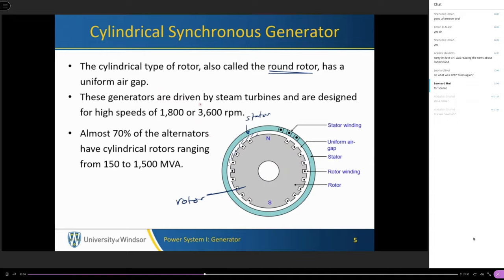These generators are driven by steam turbines and are designed for high speeds. Why? Because when we have a round rotor, we cannot make many poles. For instance, here we have the north and the south, only two poles. So this rotor has only two poles. We cannot increase the number of poles when we have a round rotor, because of the magnetic field generated by the coil.